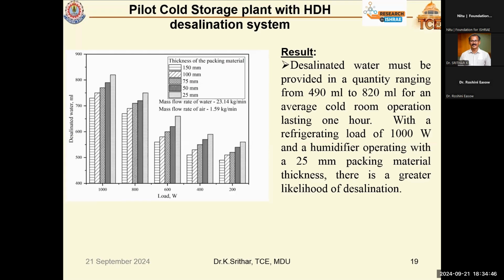lower packing material thickness. When we have a 25 mm packing material thickness, for all the loads, that is full load, 1,000 is full load of the refrigerator, 800 is 75%, 50%, and 25%, and 20%. So for all, 20, 40, 60, 80, and 100% load, the lower thickness and placing at the topmost position will give better results. We are getting better desalinated water, up to a maximum of 800 milliliter per hour additional. It is an additional outcome, apart from the saving of the COP: producing a little bit of desalinated water is an additional effect of this pilot storage plant.